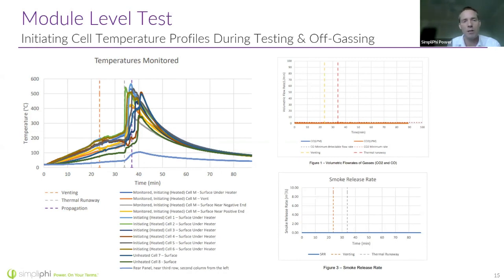And then those heaters continue to heat the cells up, and all of a sudden, around 35 minutes in, you see a rapid spike in temperature. Okay, that rapid spike in temperature is occurring when the flammable gas that's coming off the cells can actually burst into fire, right? And that releases more heat, more temperature. However, what you can see is with this particular battery module, it didn't just continue to go up in flames. The rest of the 300 or so cells within that module did not catch fire, and you can see the temperature of these battery cells gradually decline after the off-gassing event.